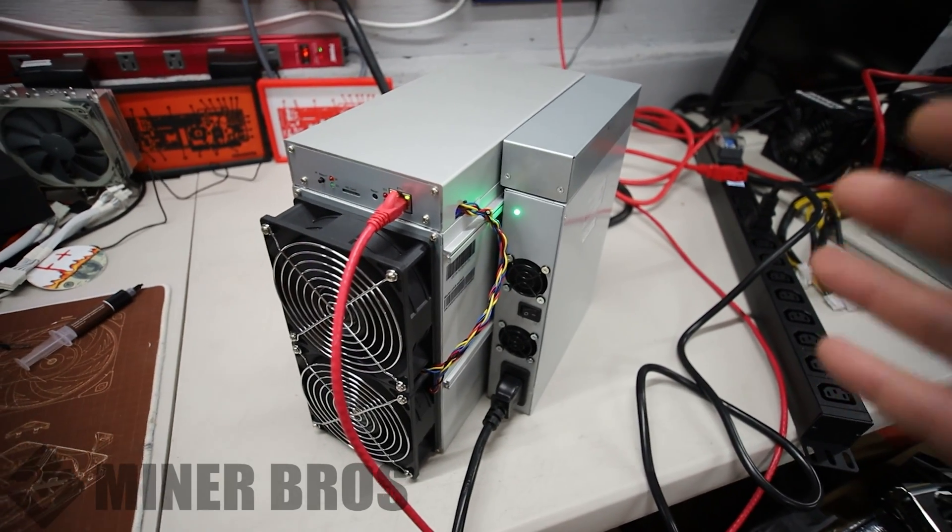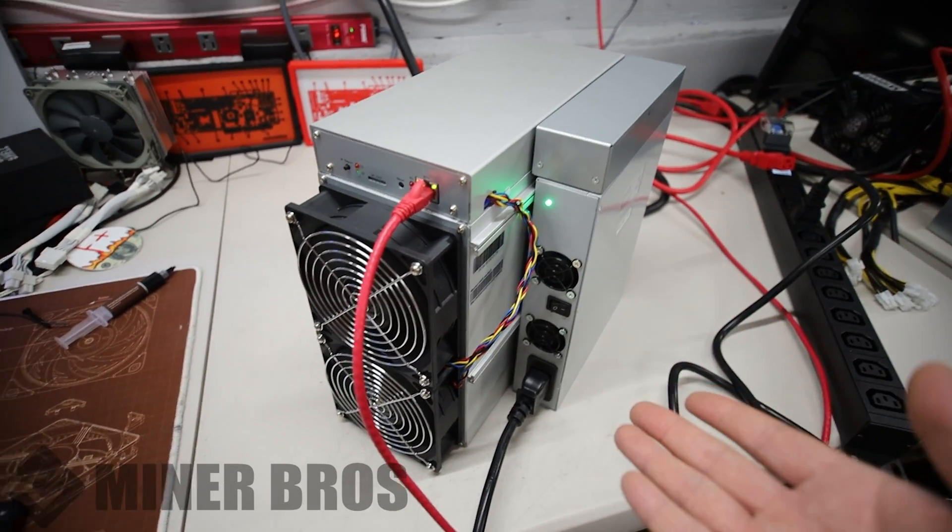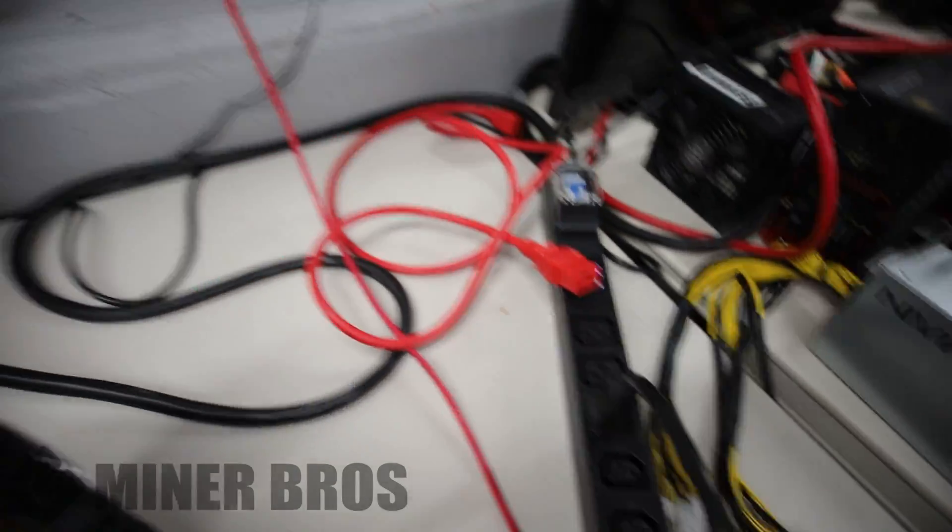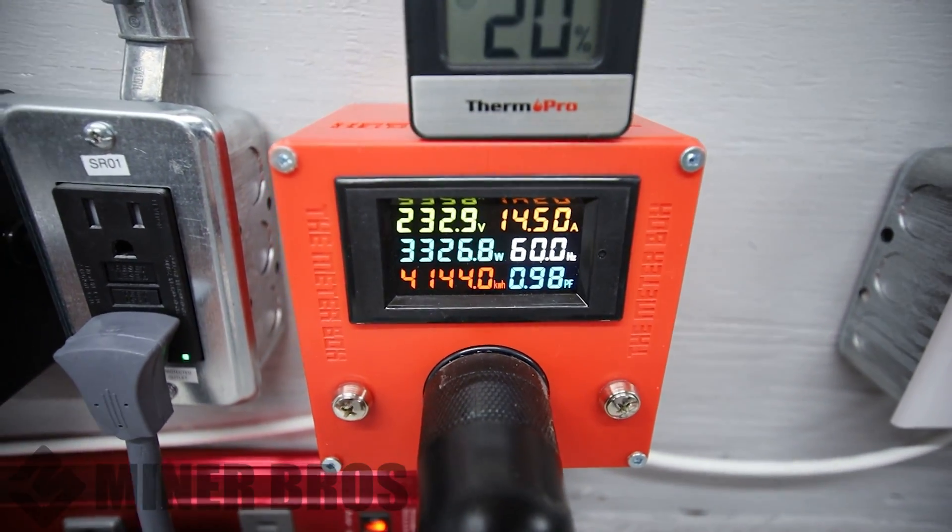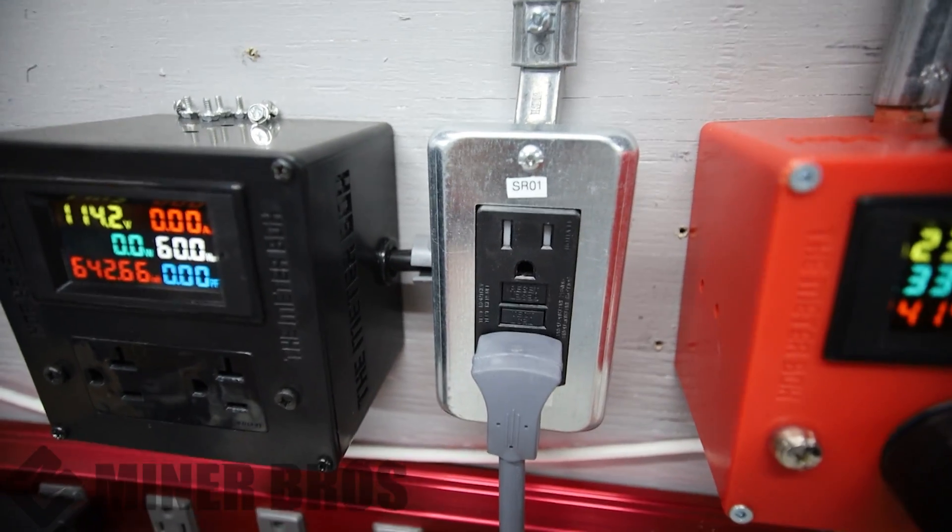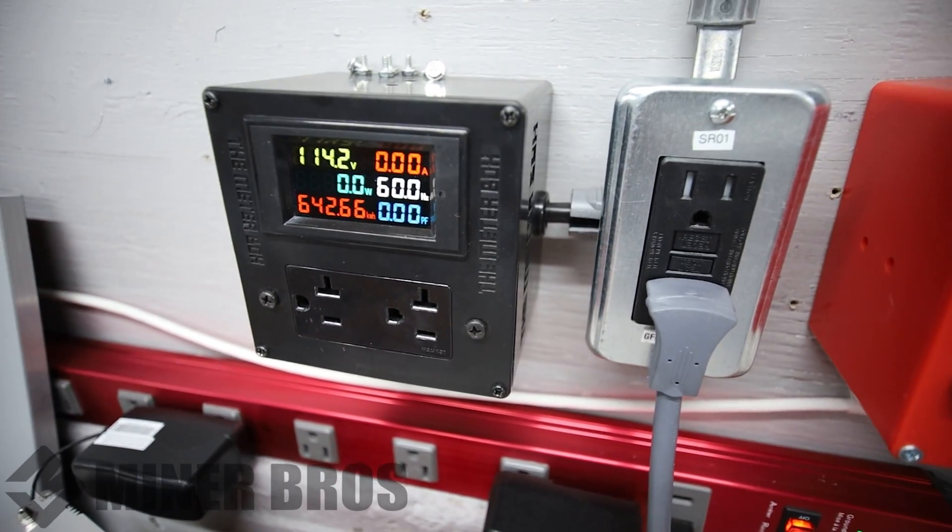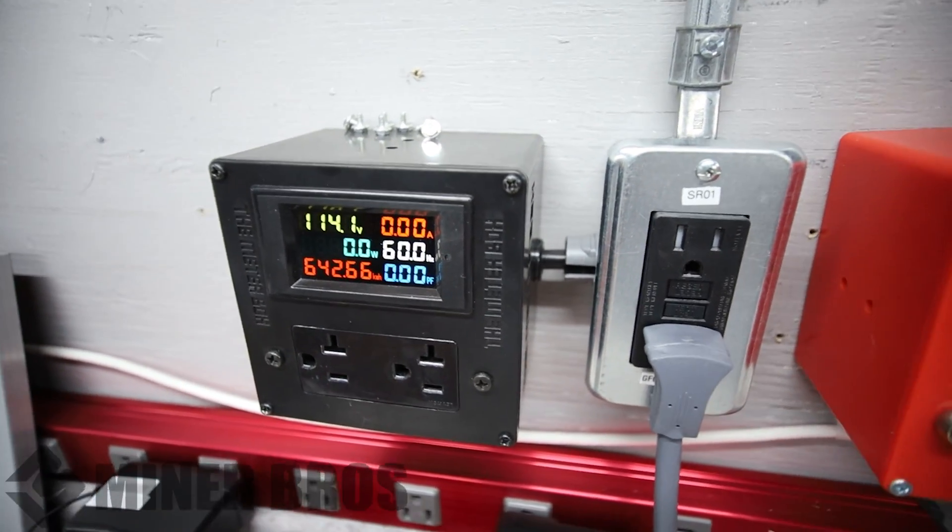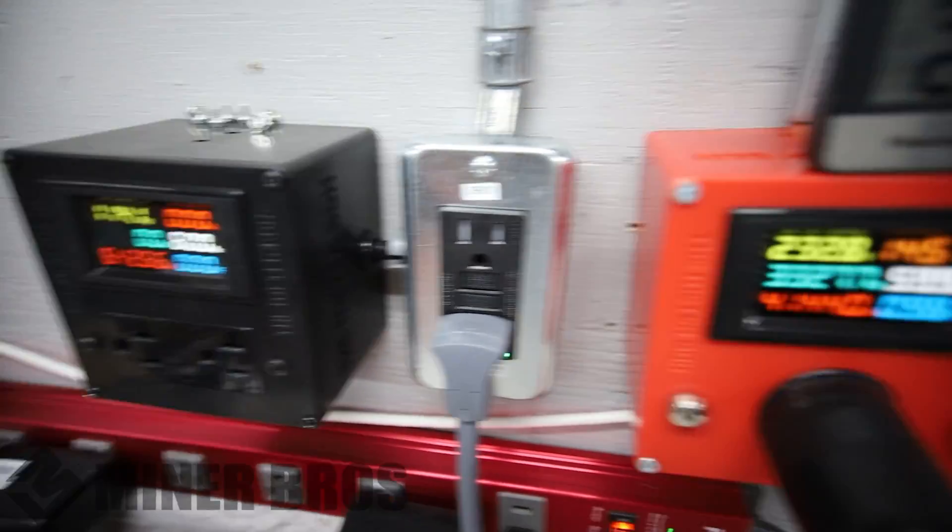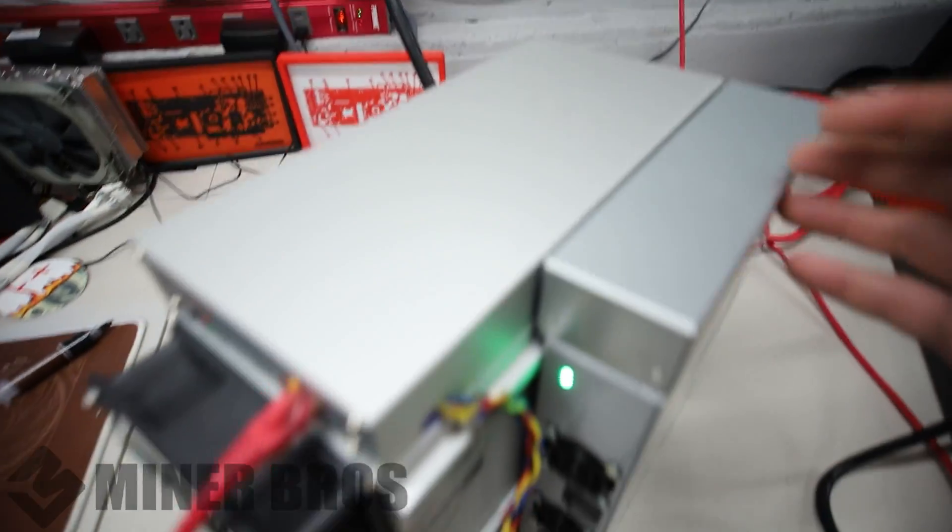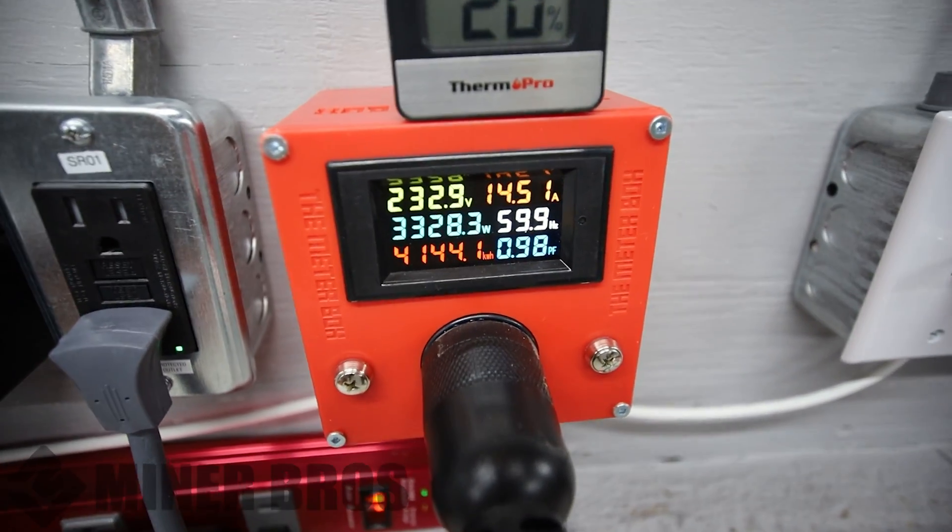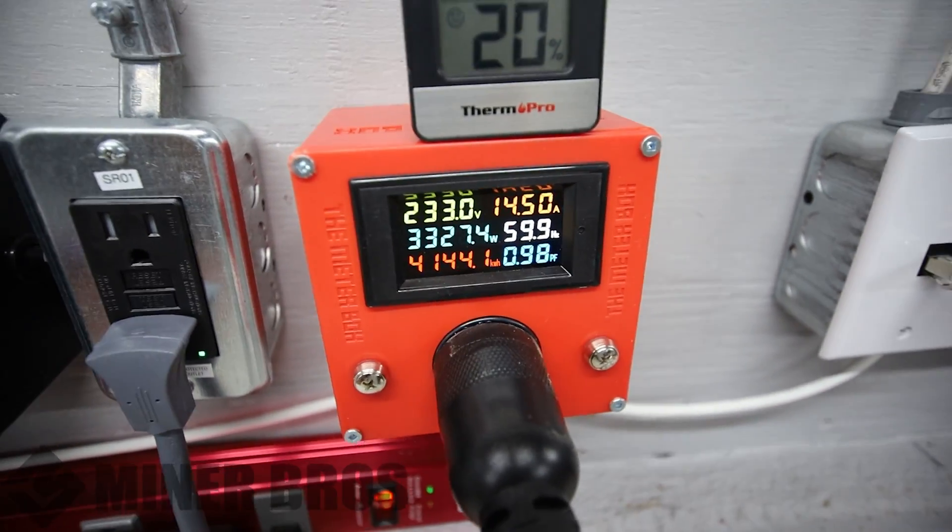For those that are wondering what is needed to run an Ice River KS3, even before you buy one of these things, it's going to come down to your power infrastructure. You're going to need to run one of these guys on a 240 volt 30 amp circuit. On a typical North American plug, like a 15 amp 120 volt circuit, it will not work. It is not enough power because these are only able to go up to about 1800 watts. But 80% rule, it's about 1400, 1500 watts. Understanding that, this 120 volt plug will not be able to run a 3000 plus watt ASIC miner, big boy ASIC miner like the Ice River KS3.